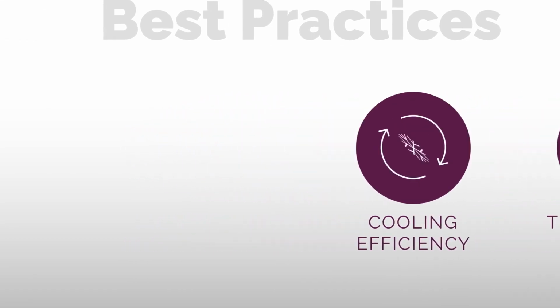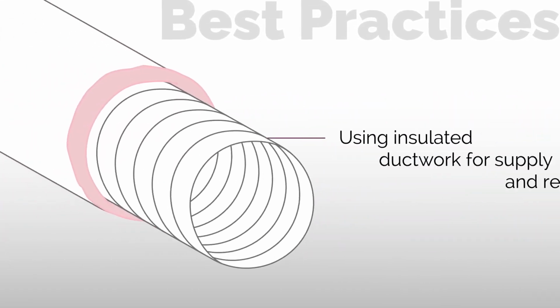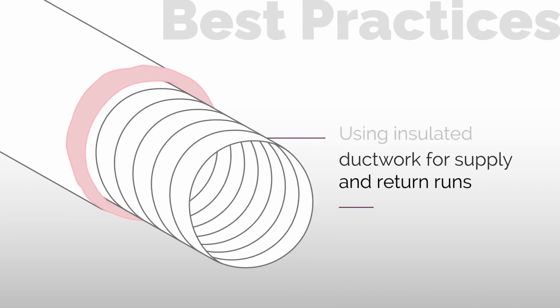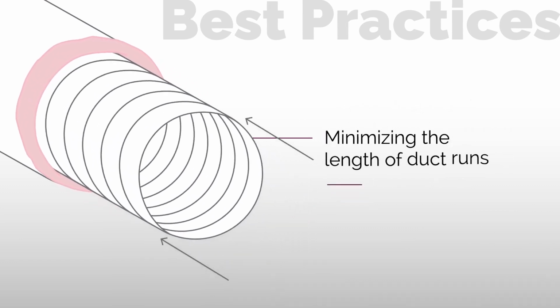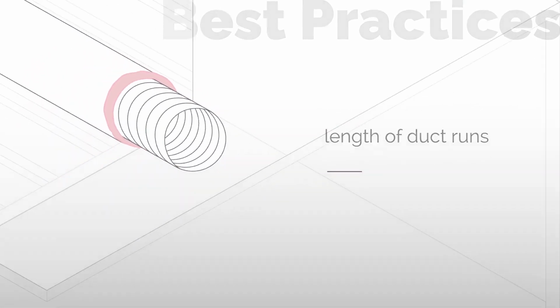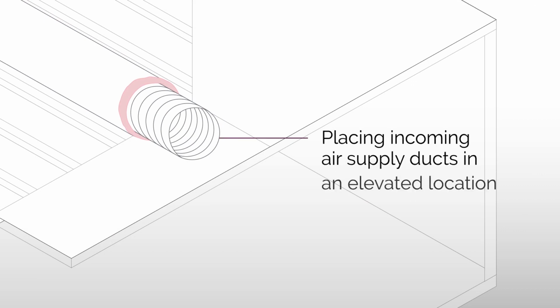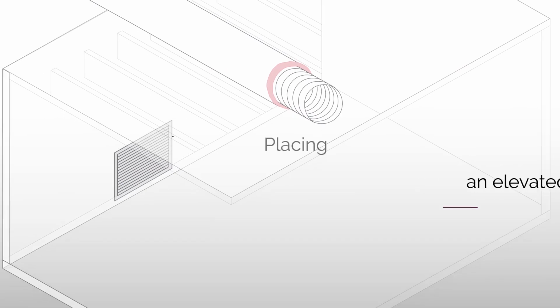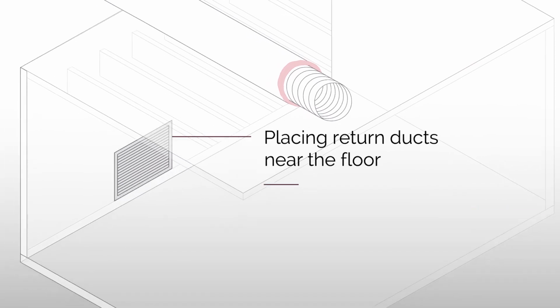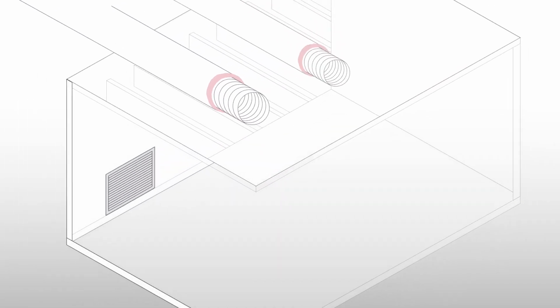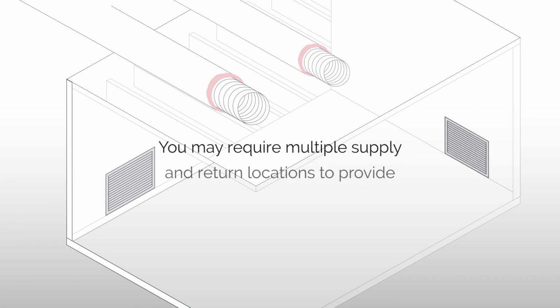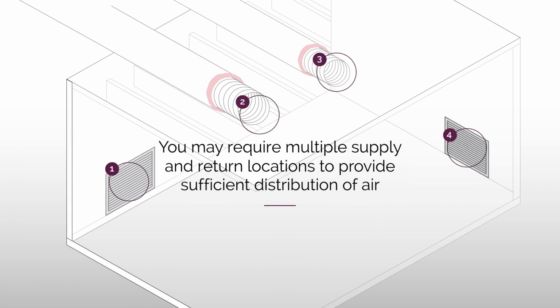temperature stability. This includes using insulated ductwork for supply and return runs, minimizing the length of duct runs where possible, placing incoming air supply ducts in an elevated position in or near the ceiling, and placing return ducts near the floor. Depending on the size of the wine wall, you may require multiple supply and return locations to provide sufficient distribution of air to all areas of the wine room.